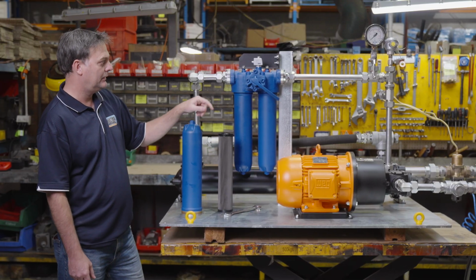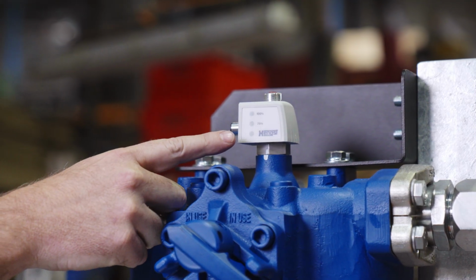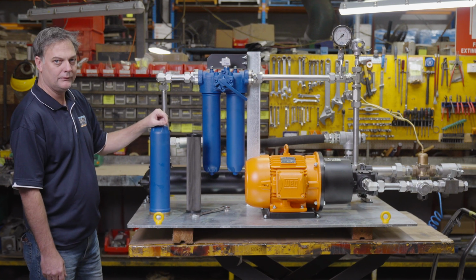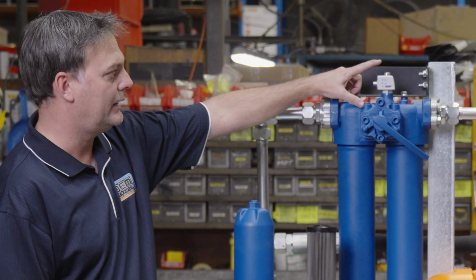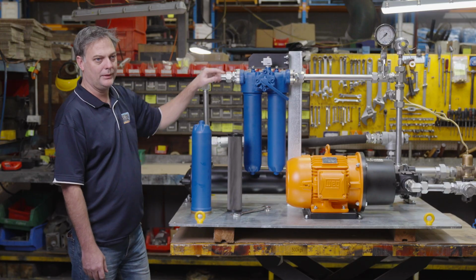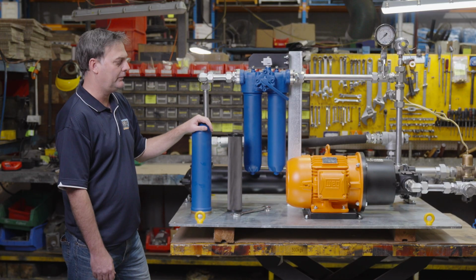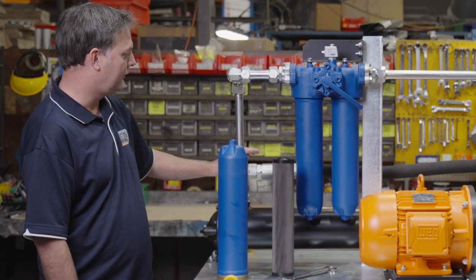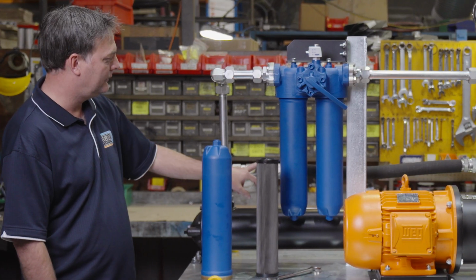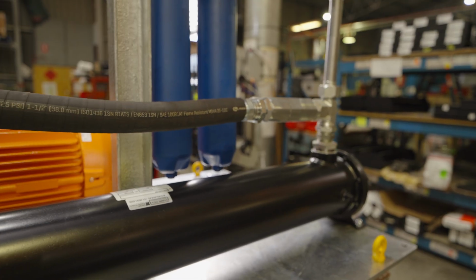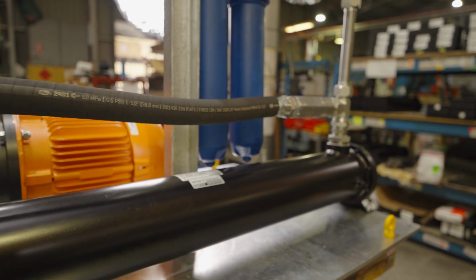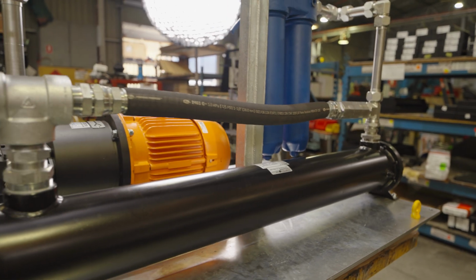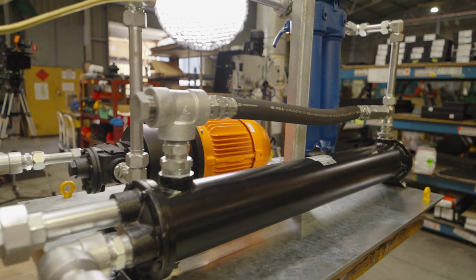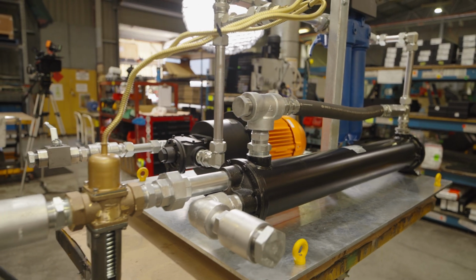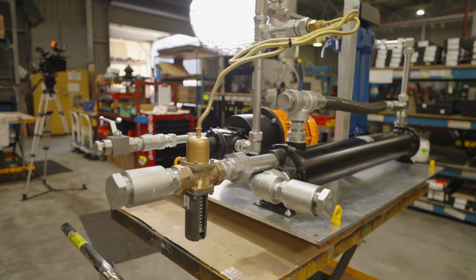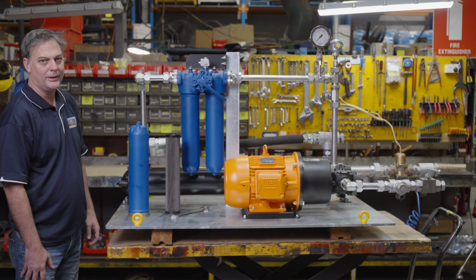Filter units, typically we offer them with electronic indicators as well as visual indicators. If the filter element's clogged, the indicator will pop up and that can be connected back into the site's electrical system for fault monitoring. This heat exchanger, we've set it up with a bypass system, so to prevent overpressurizing. So should the heat exchanger get clogged or should there be any other issue where the oil may potentially be really thick and exceeding the required pressure exerted back on the pump, it will bypass and then exit and then go back to the gearbox.